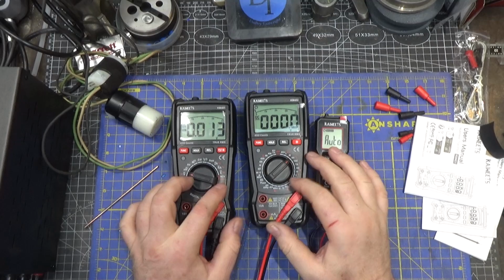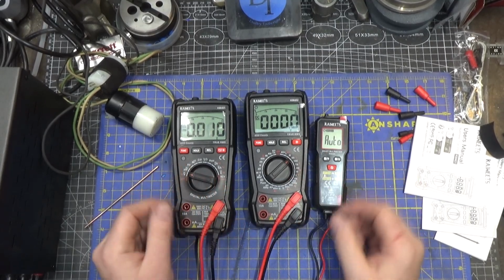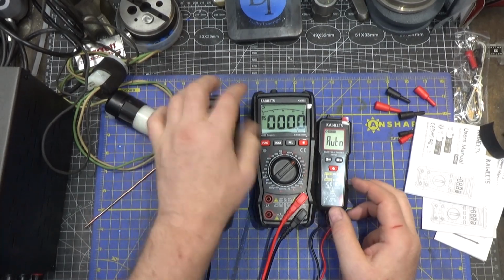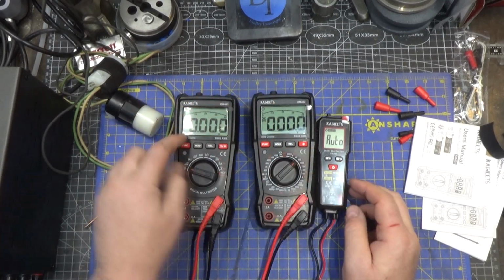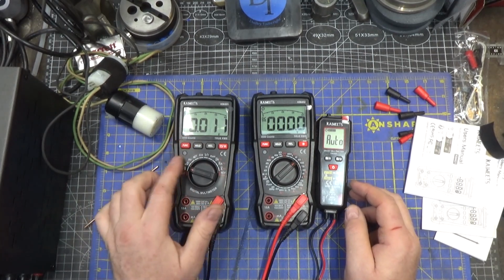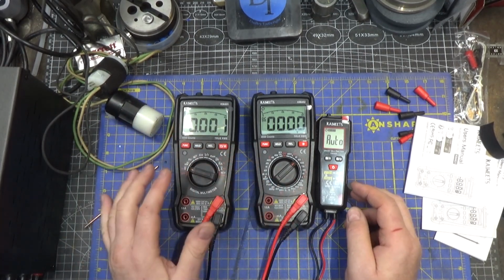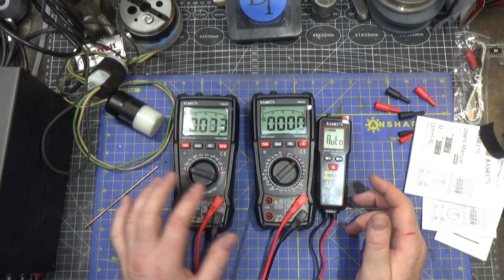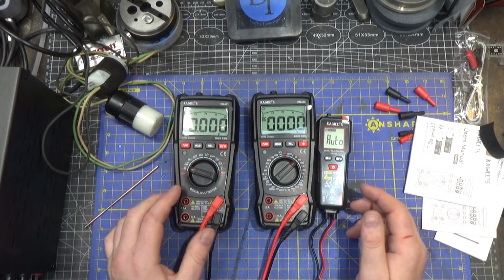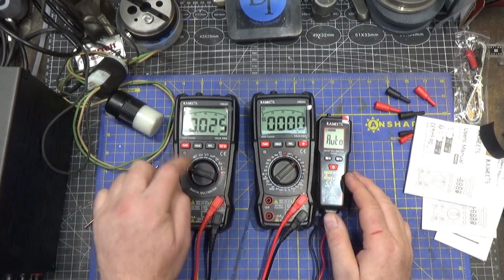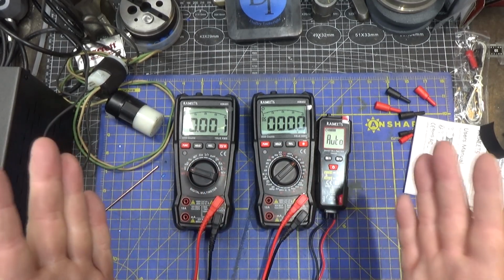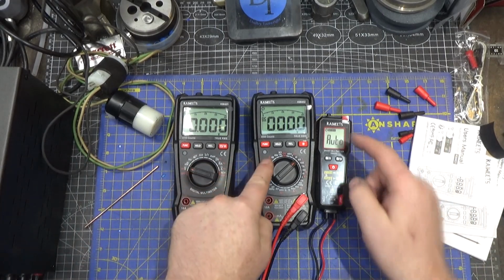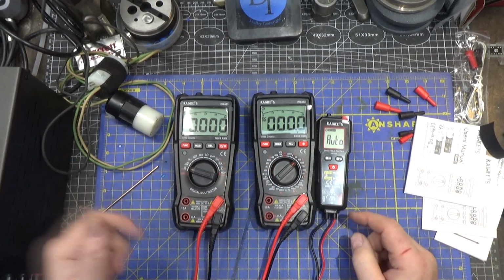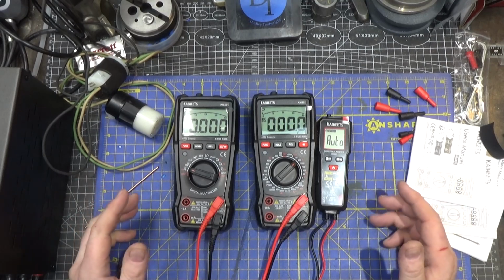Let me give my overall opinion. Back to non-contact voltage and live testing, one that uses the probe, one that uses the little sensor here. The non-contact voltage works best on these two. This one gets it eventually, and tends to work better when there's a load. So with an unloaded electric circuit, they struggle a little bit to find it. These two are much better than this one. Maybe this one's got an issue. The phase detection worked on this one, partially on this one, not really on this one at all. I think that's sort of a gimmick.